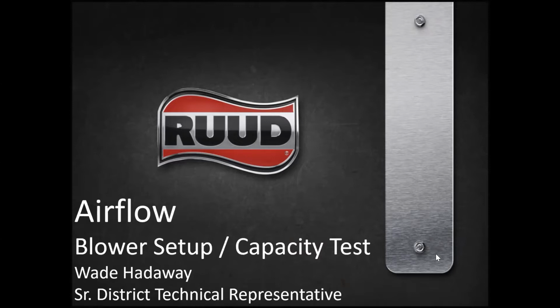So today we're going to talk about airflow. We're going to talk about how to measure airflow. We're going to talk about how to properly set up your blower to deliver the airflow that's needed for whatever matchup we're working on. And then we're going to round things out by walking through how to actually measure and calculate the cooling capacity that your system is operating under. The last thing we're going to talk about today is what numbers we need and how to plug them into a formula to tell you exactly how many BTUs a particular system is removing from the conditioned space. That can be really helpful in solving problems and diagnosing issues, especially if you have a customer, homeowner, property owner, or tenant who is complaining that the system's not keeping up.